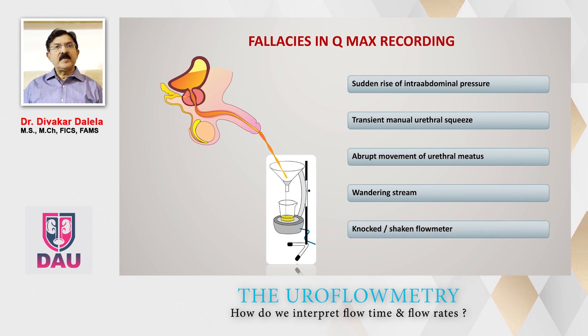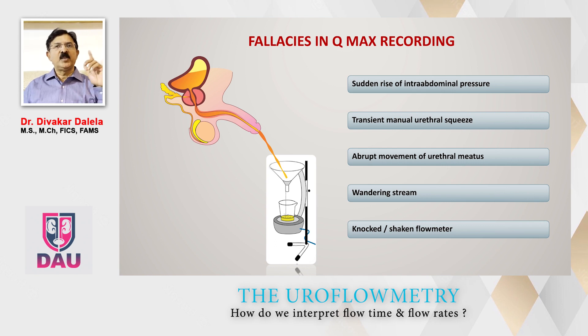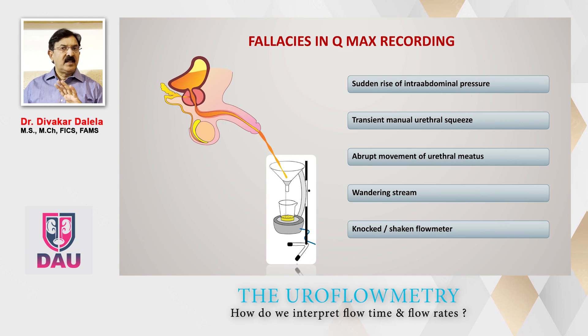Sometimes the patient's shoe touches the stand or the uroflowmeter machine — this is called a knock or a shaken flowmeter — and that results in an aberration giving a spuriously high Q-max. So before you interpret the Q-max values on a patient's graph, please make sure there are no such fallacies in the record.